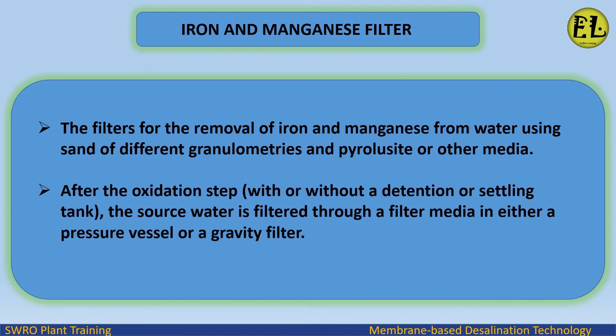Iron and manganese filters use sand of different granulometries and pyrolusite or other media for removal of iron and manganese from water. After the oxidation step, with or without a detention or settling tank, the source water is filtered through a filter media in either a pressure vessel or a gravity filter.